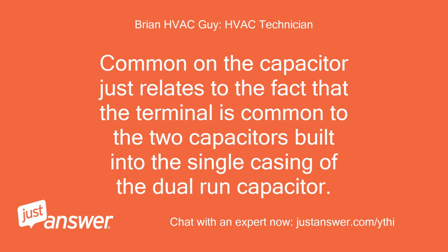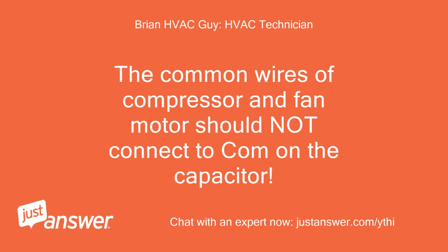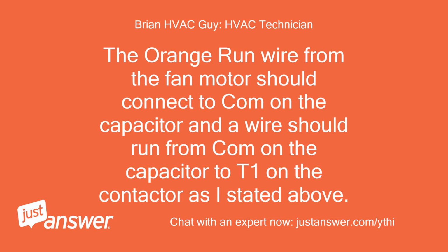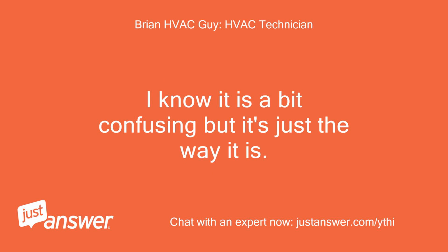Common on the capacitor just relates to the fact that the terminal is common to the 2 capacitors built into the single casing of the dual-run capacitor. The common wires of compressor and fan motor should not connect to COM on the capacitor. The orange run wire from the fan motor should connect to COM on the capacitor, and a wire should run from COM on the capacitor to T1 on the contactor as I stated above. I know it is a bit confusing, but it's just the way it is.